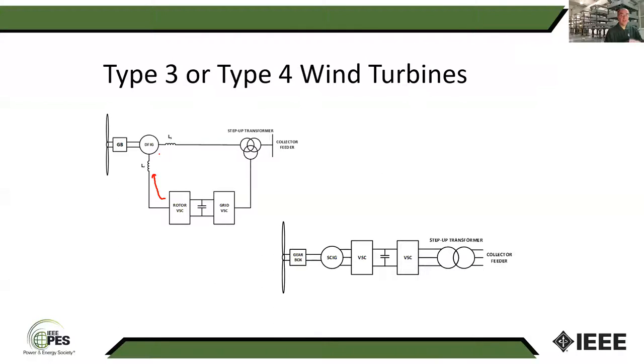So the net flux of what's coming from the machine rotation plus this injected current is going to look like the machine is turning faster than synchronous speed, so it can supply power. And so this circuit here with the two voltage source converters is basically controlled to provide power. So if this is turning much faster than synchronous speed, then you're going to have power going that way and you inject it into the system. If the rotor is turning slower than synchronous speed, you have power go this way.